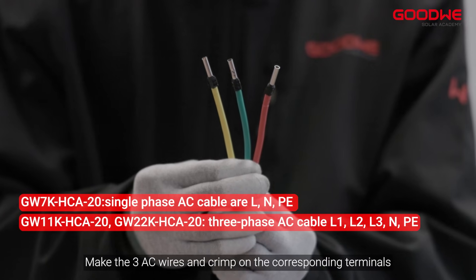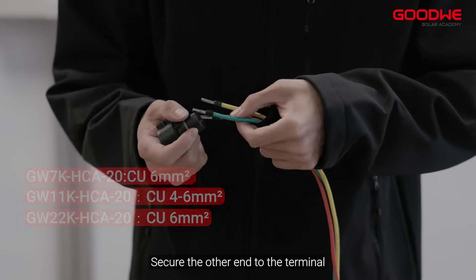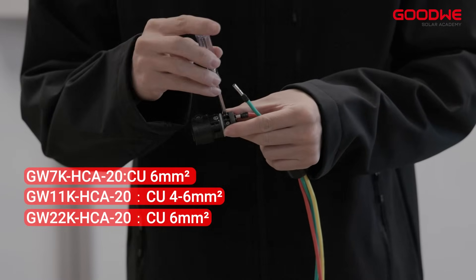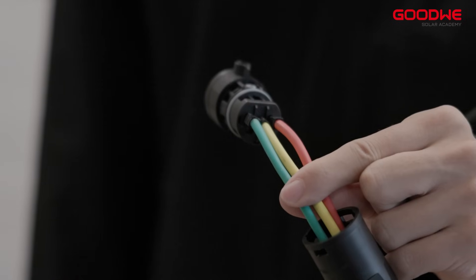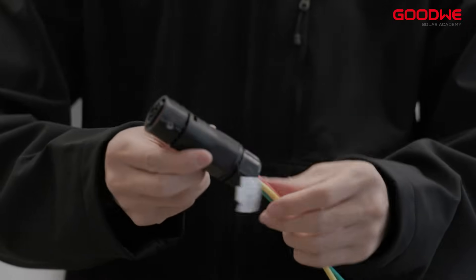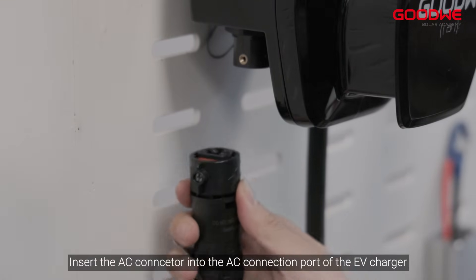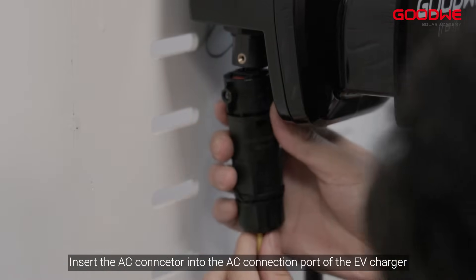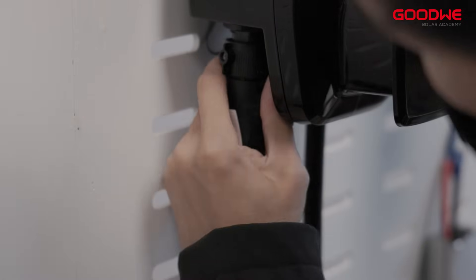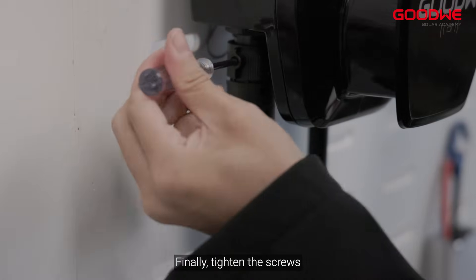Make the three AC wires and crimp on the corresponding terminals. Pass the cable through one end of the AC connector and secure the other end to the terminal. Complete the final fixing of the AC connector. Loosen the screws on the side of the AC connector and insert it into the AC connection port of the EV charger. Finally, tighten the screws.